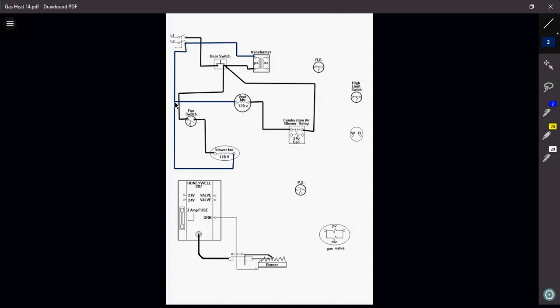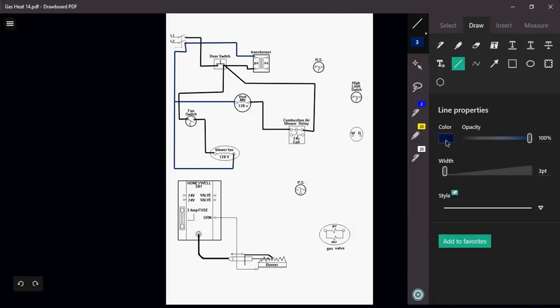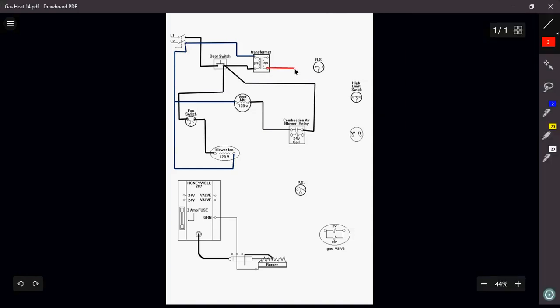Now we're going to get into our 24 volt side, the control side of it. 24 volts, that controls everything. It's known as the control voltage. Okay? So, in order for me to even get 24 volts, I got to power up my transformer on my 24 volt side, right? So here, we got red. Red is going to come out of my transformer, and I'm going to come right into my thermostat, right? R. Red. Okay, red wire on a thermostat is my 24 volt power.